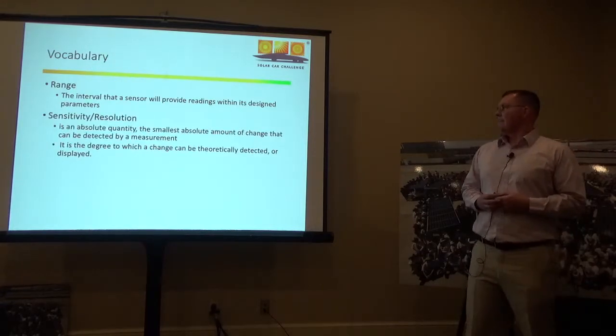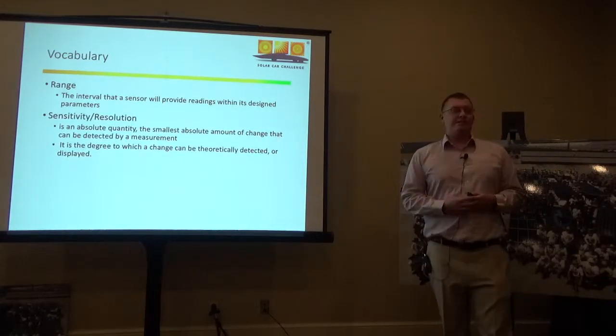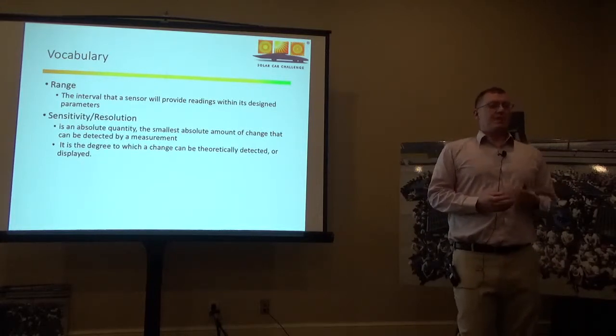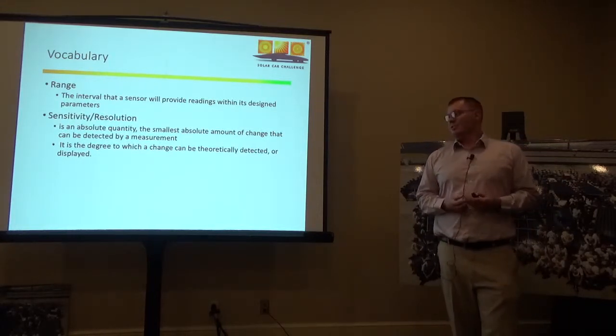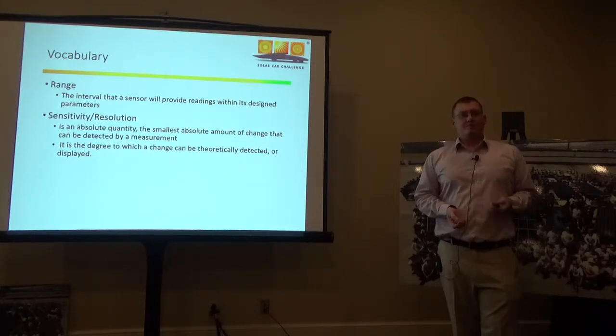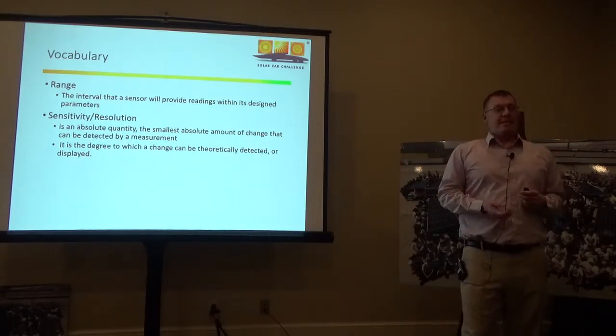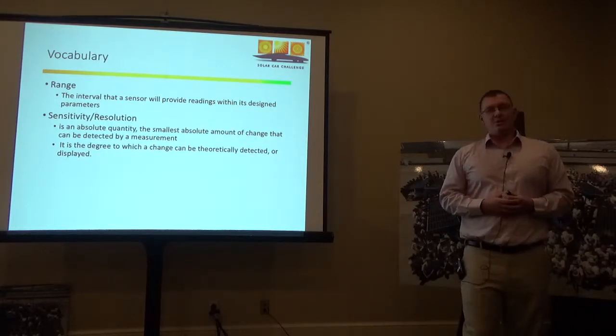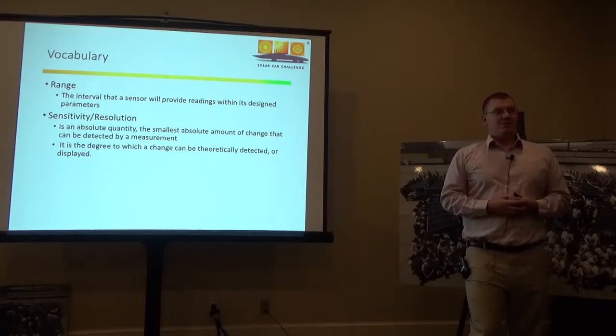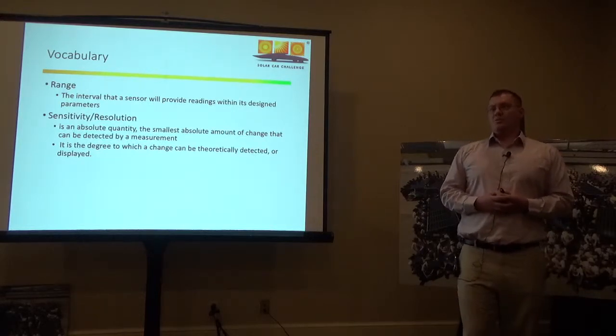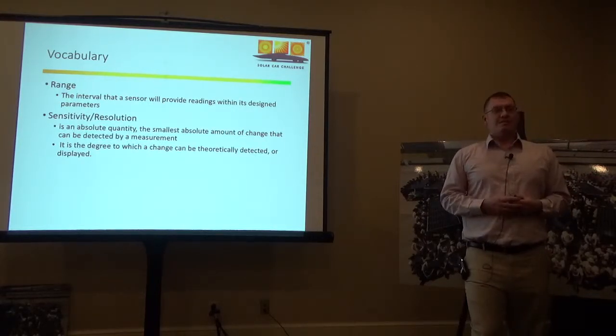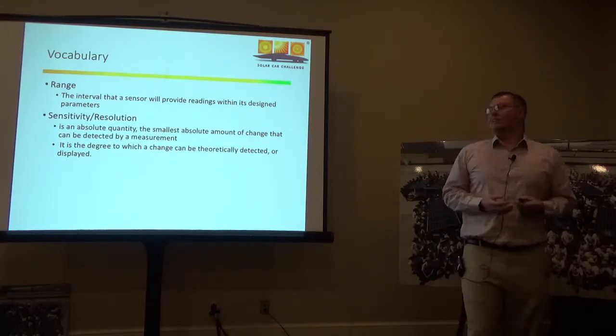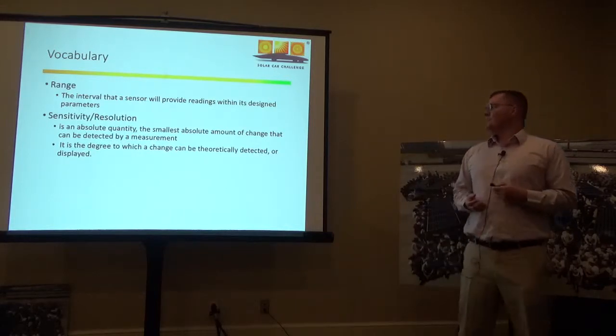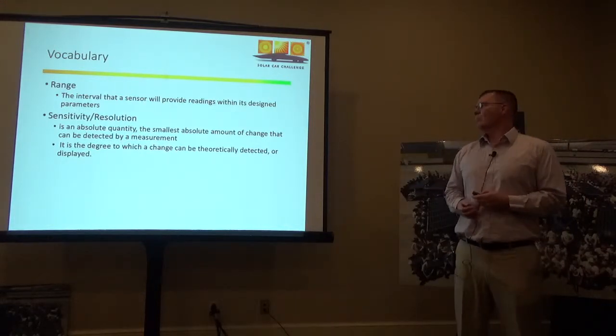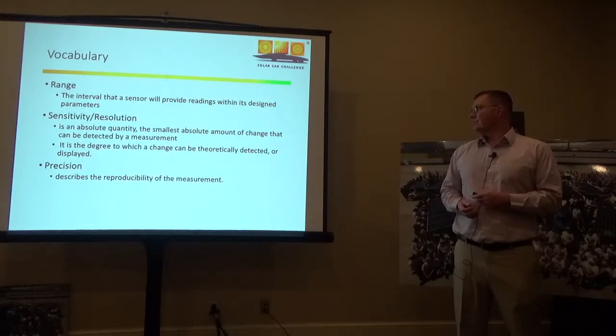Sensitivity, plus resolution, is an absolute quality inherent in the system. It's the smallest amount that sensor can measure. For example, in my telemetry system, my voltage at one point was going out to 12 decimal places, but my sensor is only good to a thousandth. So anything beyond 3 decimal places was just noise, no point having that. You have to know what information the sensor is good for, and what the sensitivity of it is.